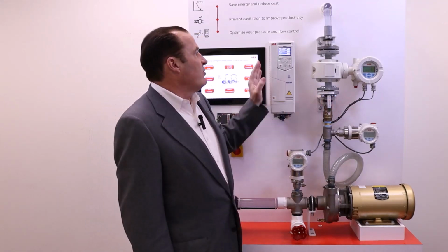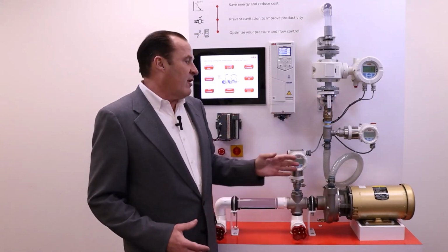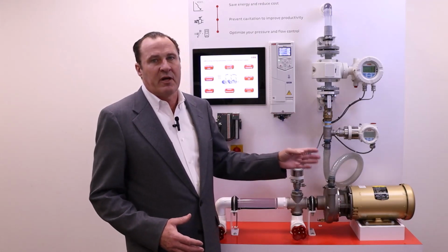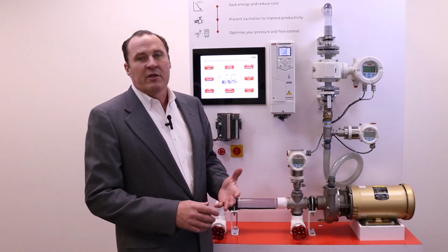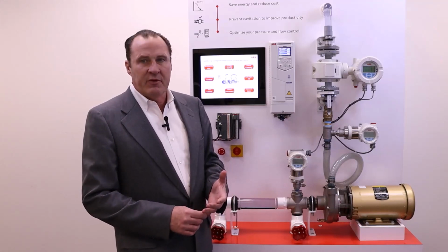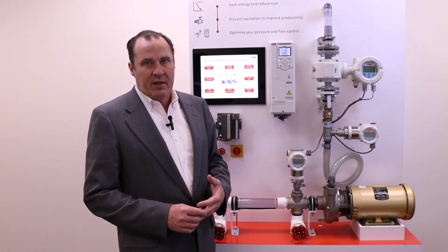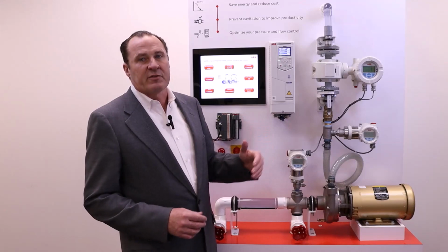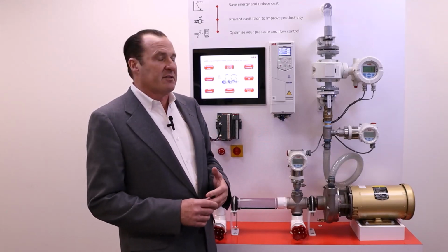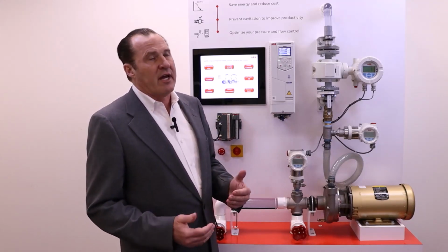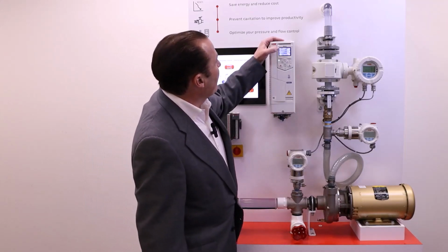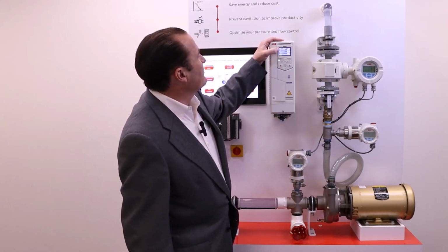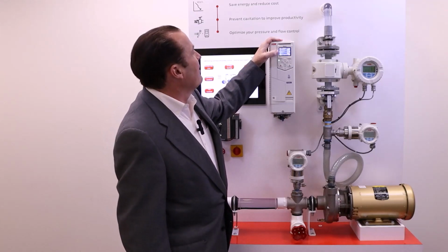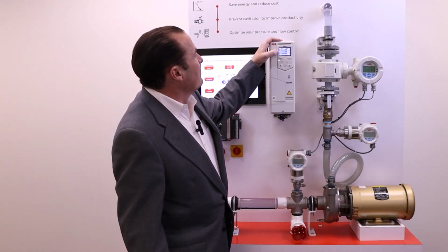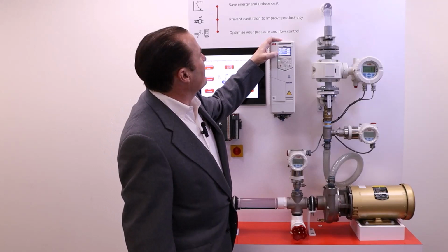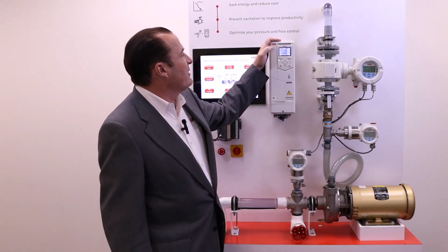This throttling valve, from fully open to fully closed, will help me collect my data points. Now, to start this out with, we need to find out the pumping characteristics of this pump and this motor. We need to know shaft horsepower, system flow, and system pressure. In this case here, I have it set up for system pressure in feet. I have system flow in gallons per minute and shaft horsepower in horsepower. On my keypad, I've set it up so line 1 is shaft horsepower, line 2 is feet of water column, and line 3 is flow, gallons per minute.